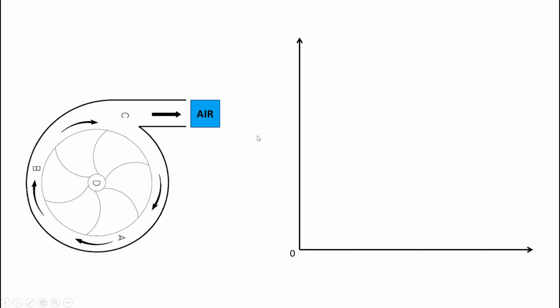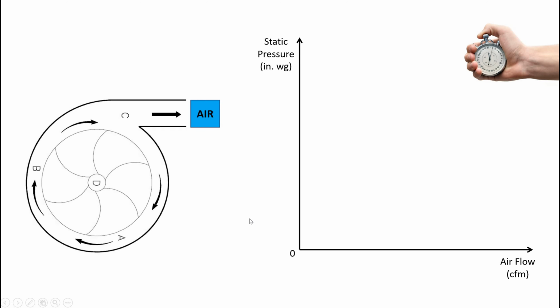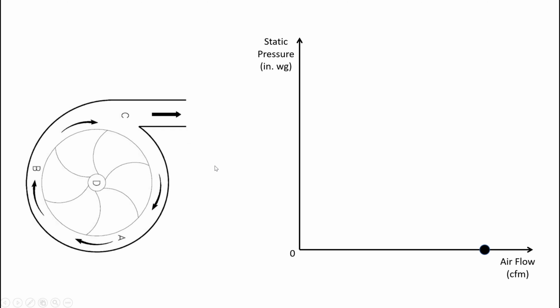On the vertical axis, we'll put static pressure. On the horizontal will be airflow. Each fan has a value of airflow without resistance. It's also called free delivery. Also, each fan has a static pressure without airflow value. Let's say we close the fan discharge and measure the pressure. Let's say it will be this value. In between these two values will be a chart like that, which is called the fan curve.